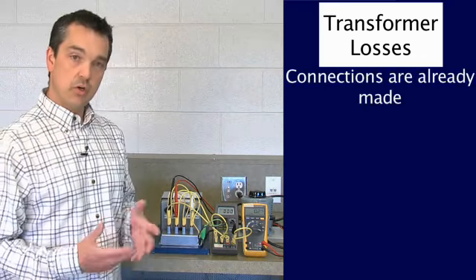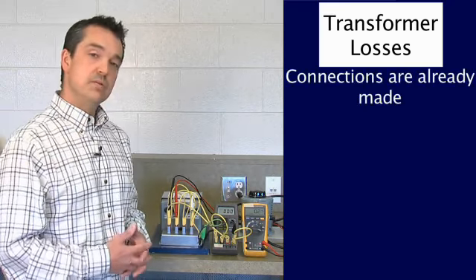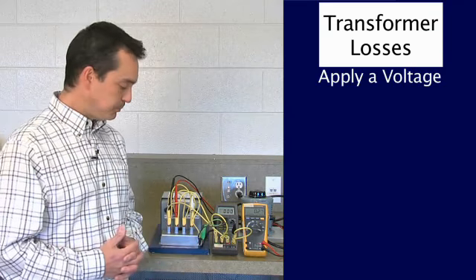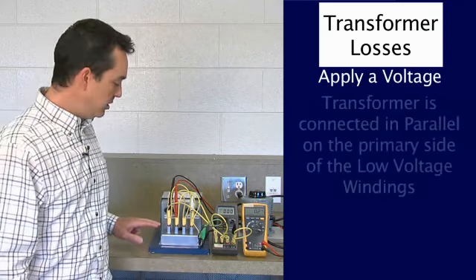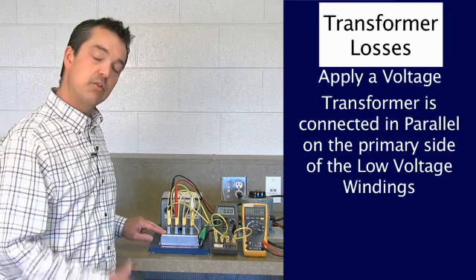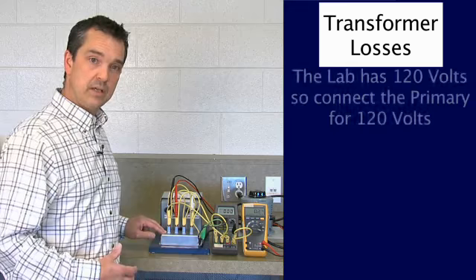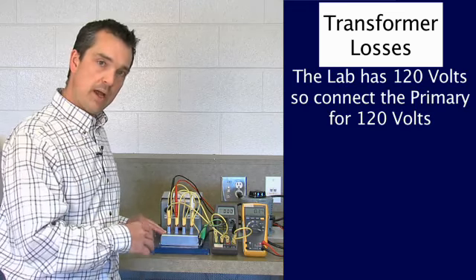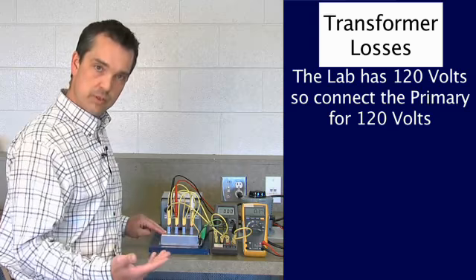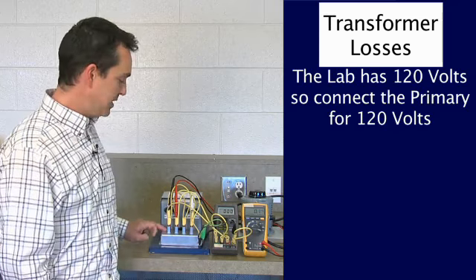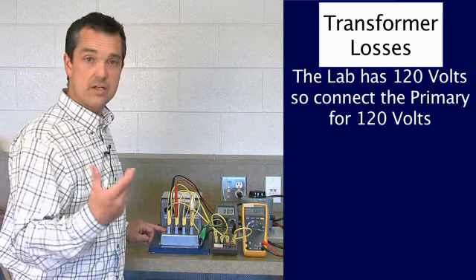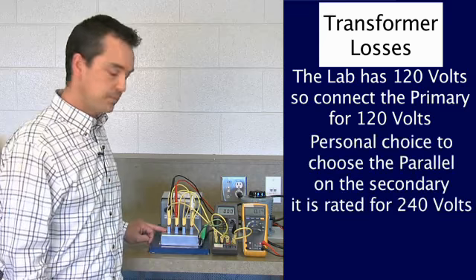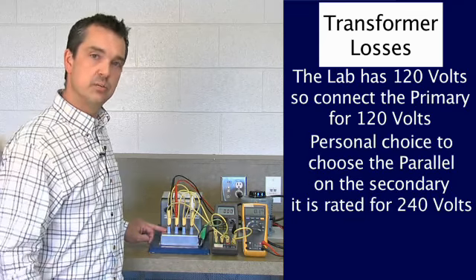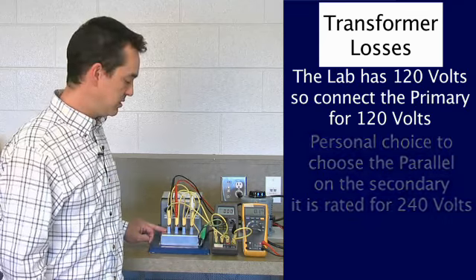So at this point in time, I have it already connected, and what I'm going to do is apply a voltage to it and see what's actually going to happen. My transformer is connected in parallel on the primary side for my low voltage windings. The reason I'm doing that is because I have 120 volts available in the lab, so I connected my primary for 120 volts, the appropriate voltage supply. My secondary, I chose to select a parallel connection on my secondary, so the secondary is rated for 240 volts. I can change that around if I like to, but that's just what I chose for the test. So I have 120 volt rated primary and a 240 volt rated secondary.